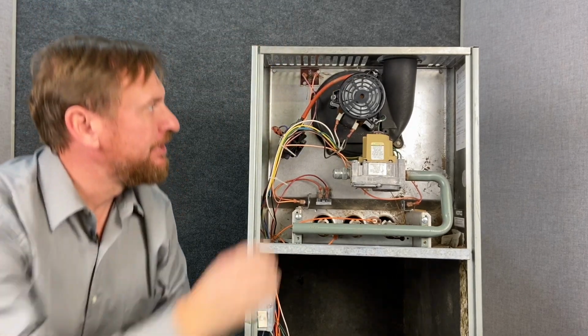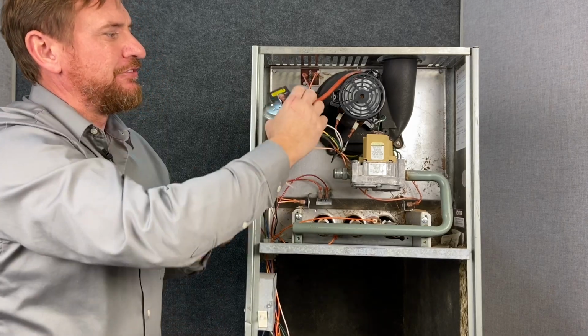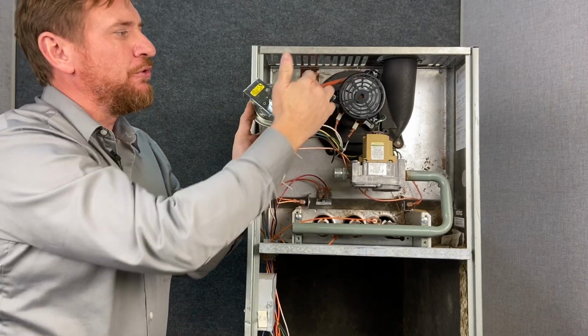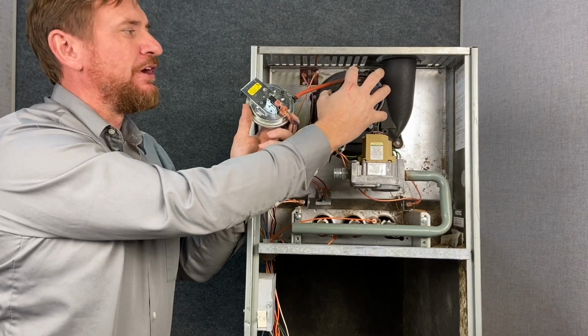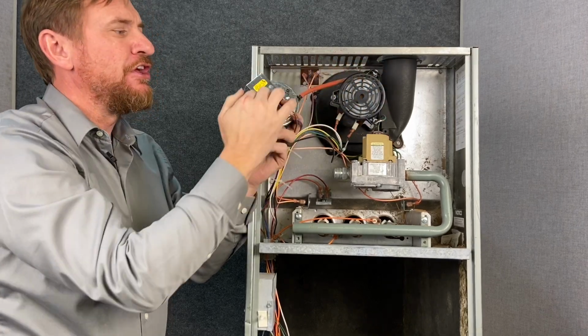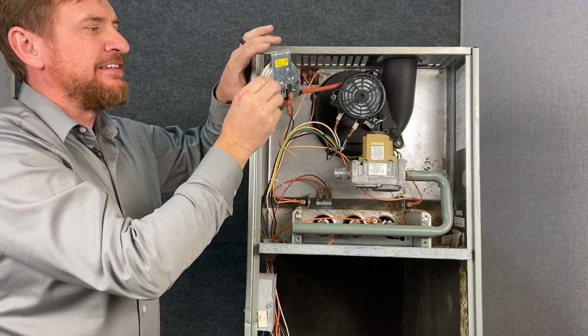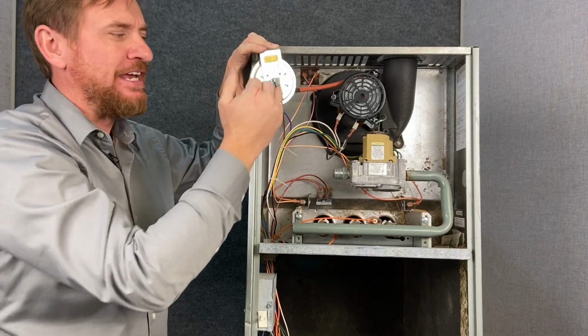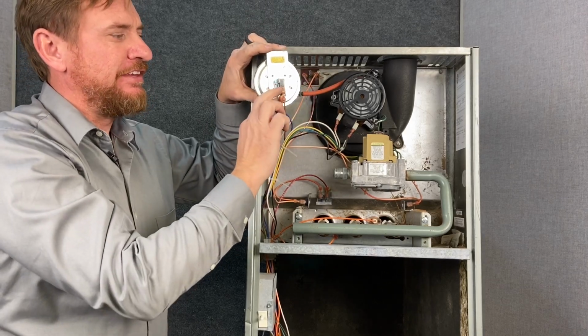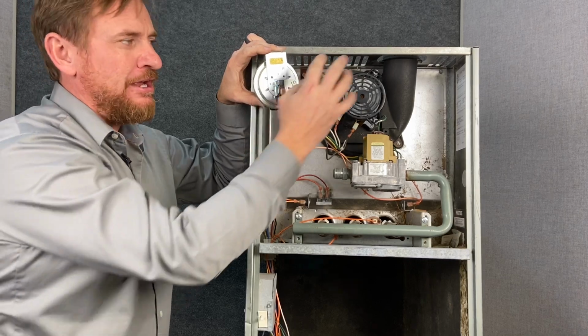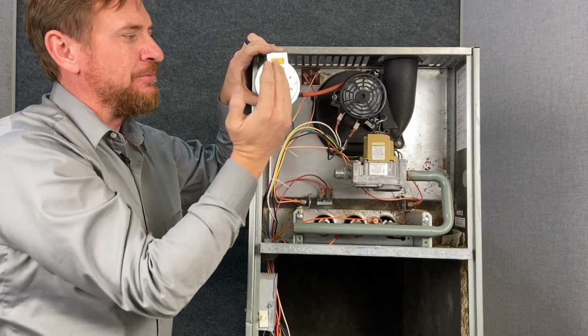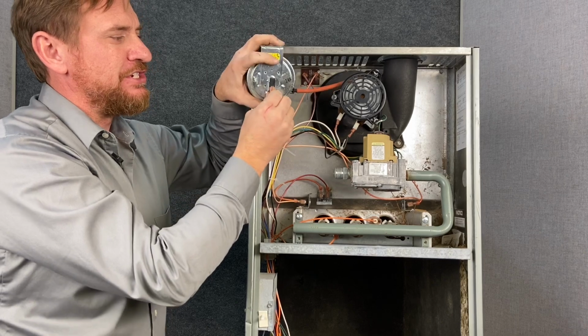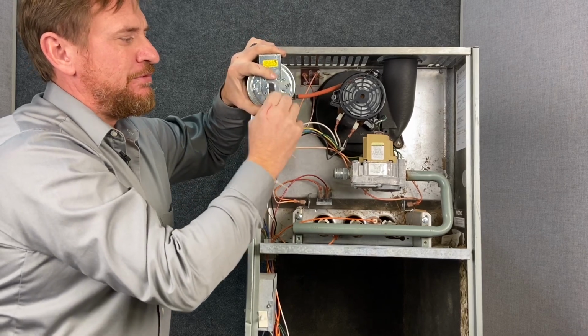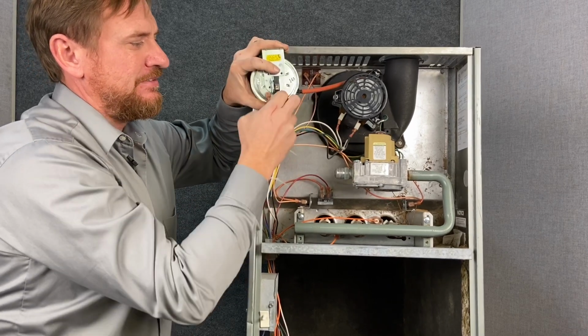Right, 2 screws are free. Now we have the mounting of this free. So we have a hose coming to it. So when this inducer fan motor runs, it pulls a vacuum through this hose to our pressure switch, or I like to teach it as a negative pressure switch. It activates on negative pressure. These 2 terminals are normally open. When this motor runs, it pulls a vacuum, pulling a diaphragm, closing this switch. So if we want to disconnect this, we just disconnect these 2 wires.